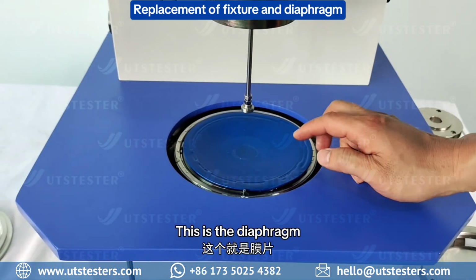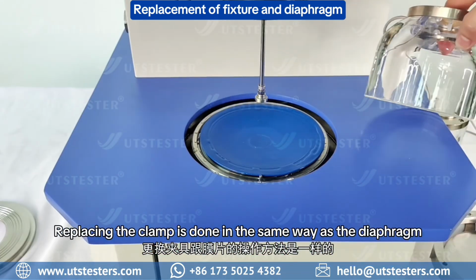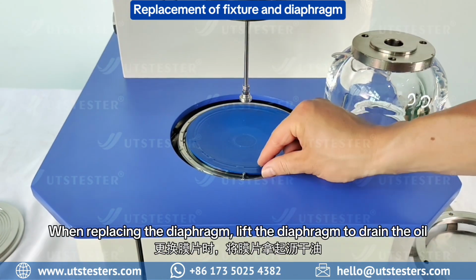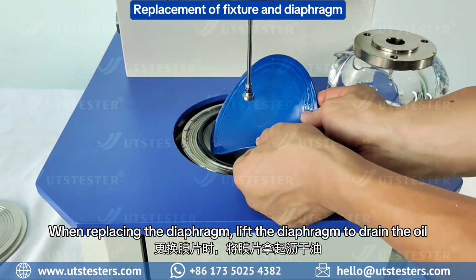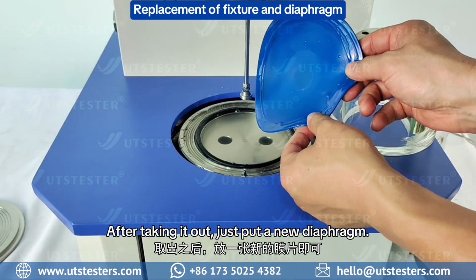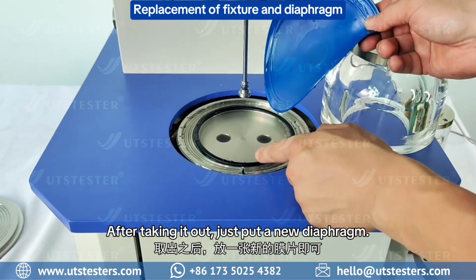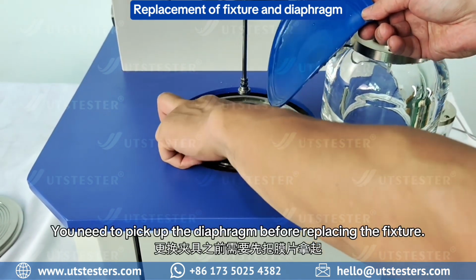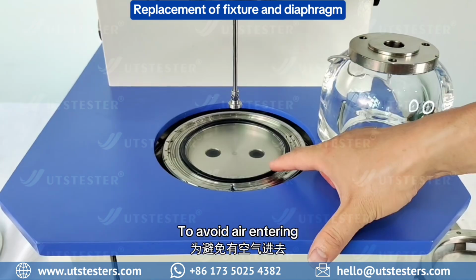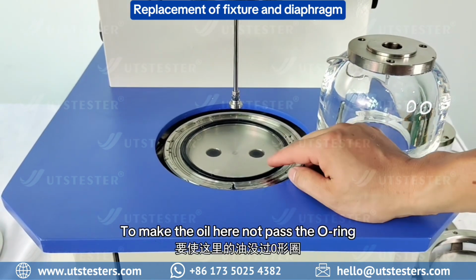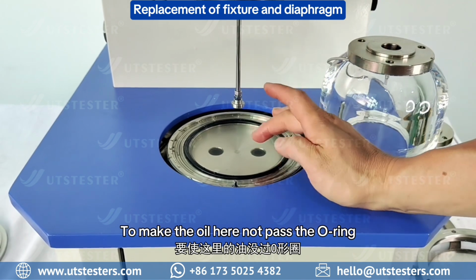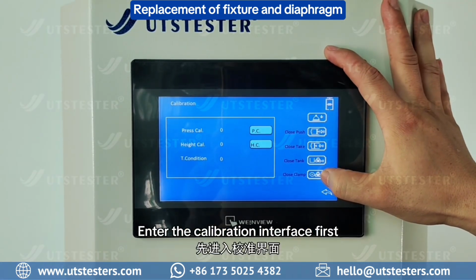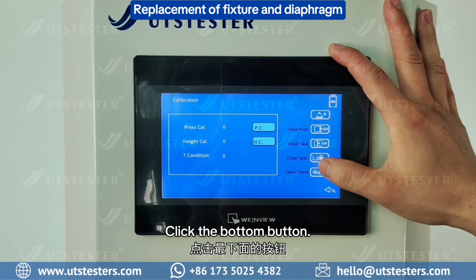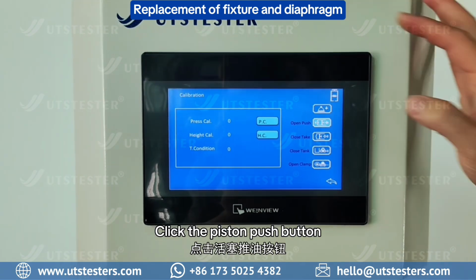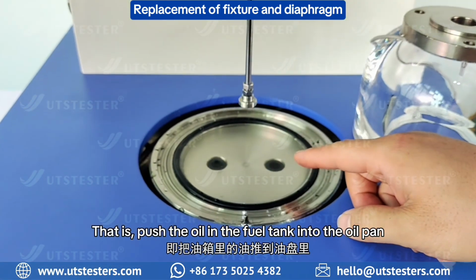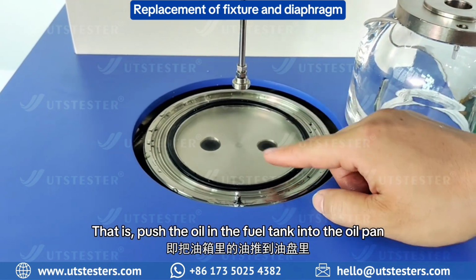This is the diaphragm. Replacing the clamp is done in the same way as the diaphragm. When replacing the diaphragm, lift the diaphragm to drain the oil. After taking it out, just put in a new diaphragm. You need to pick up the diaphragm before replacing the fixture to avoid air entering. To make the oil here not pass the O-ring, enter the calibration interface first. Click the bottom button. Click the piston push button. That is, push the oil in the fuel tank into the oil pan.